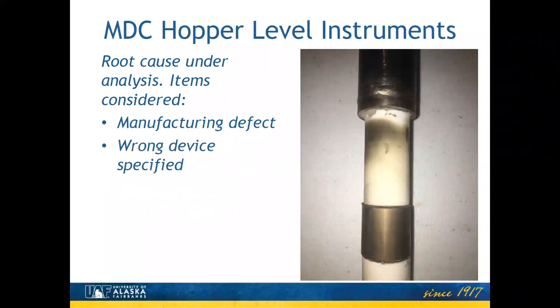So then the latest thing we're dealing with is this leveling. This is an abbreviated photo of it. It's a device that's about 2 feet long and has a radio frequency antenna at the end of it that measures the density of the material that's sitting in. And from that, it determines the level of ash in these MDC hoppers. And we sent these off to the manufacturer to get them to evaluate them.